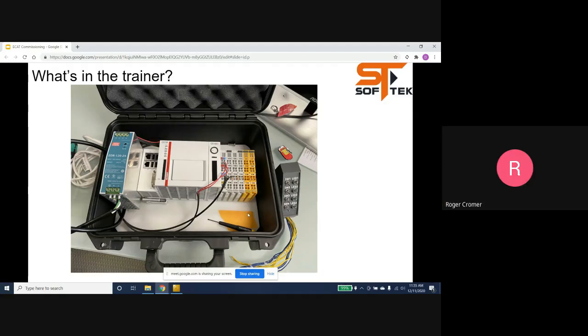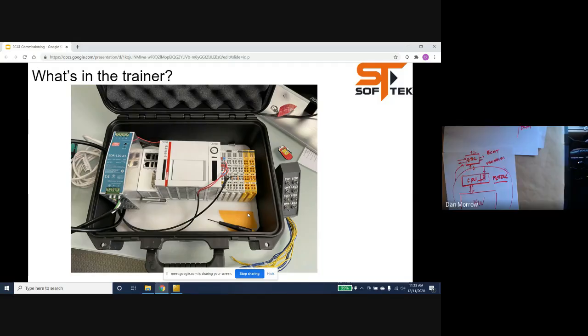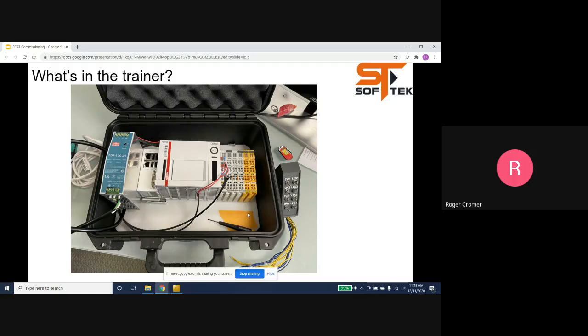That'll actually prevent the system from working completely, so it's one of the first things that needs to be done, because you won't be able to scan everything in if they've got the same dip switch settings, especially if they're similar slices. If you've got a number of these units together and they're all set to the same dip switch setting, it won't scan them all in. It'll throw an error in the system.